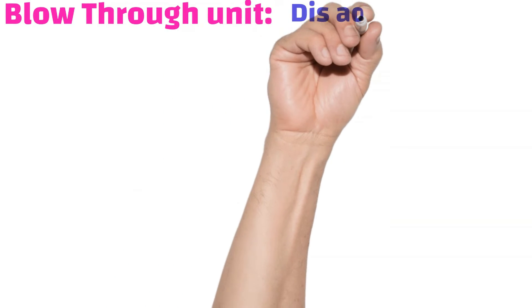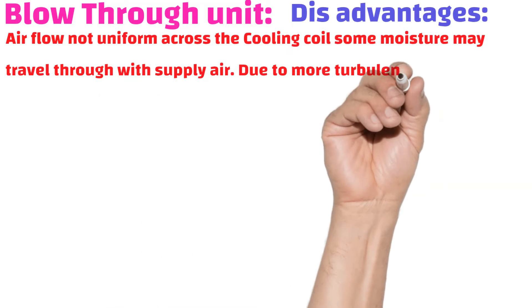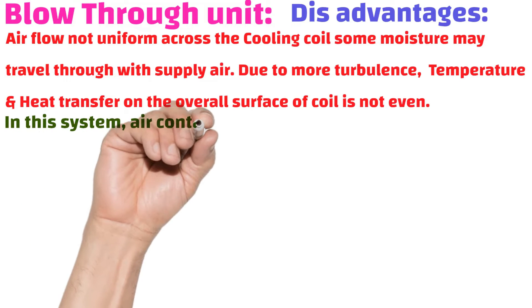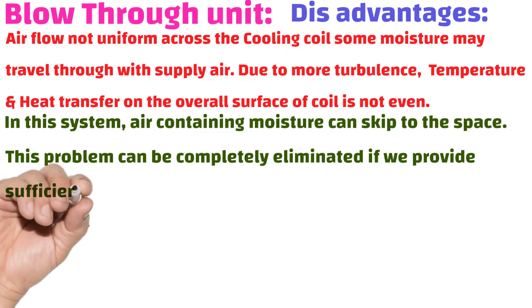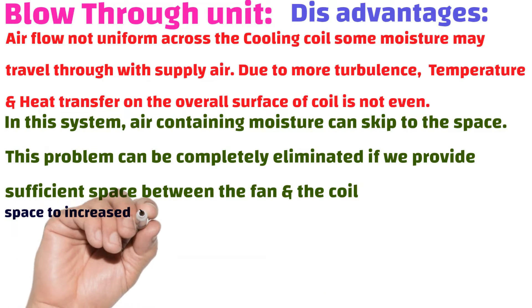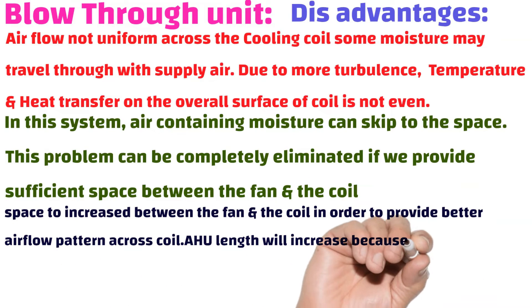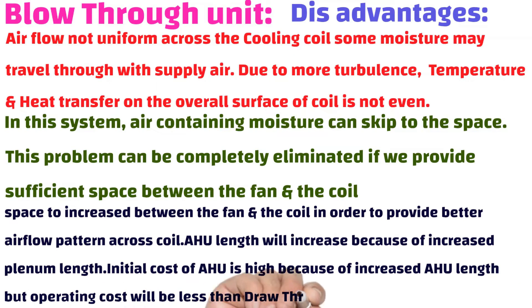Disadvantages of the blow through unit: Airflow is not uniform across the cooling coil. Some moisture may travel through with the supply air. Due to more turbulence, temperature and heat transfer on the overall coil surface is not even. Air containing moisture can escape to the space. This problem can be completely eliminated if we provide sufficient space between the fan and the coil, in order to provide a better airflow pattern across the coil. AHU length will increase because of the increased plenum length, and the initial cost of the AHU is high because of the increased AHU length.